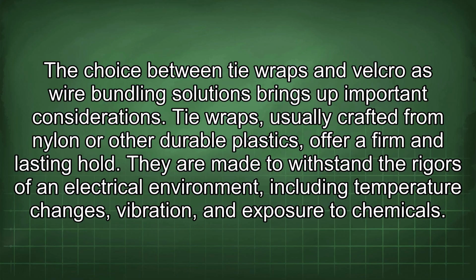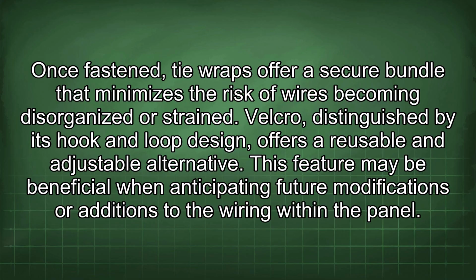Tie wraps, usually crafted from nylon or other durable plastics, offer a firm and lasting hold. They are made to withstand the rigors of an electrical environment, including temperature changes, vibration, and exposure to chemicals. Once fastened, tie wraps offer a secure bundle that minimizes the risk of wires becoming disorganized or strained. Velcro, distinguished by its hook and loop design, offers a reusable and adjustable alternative.